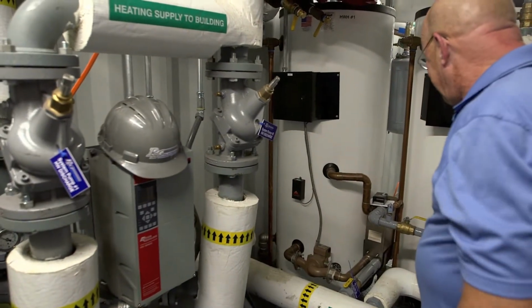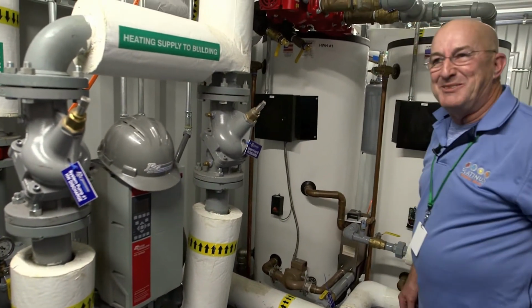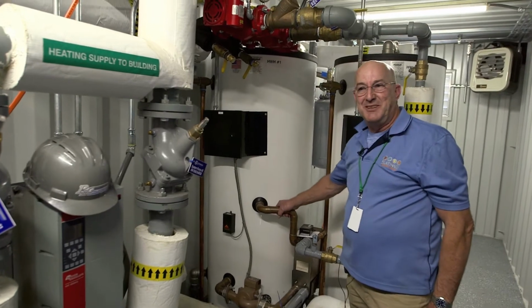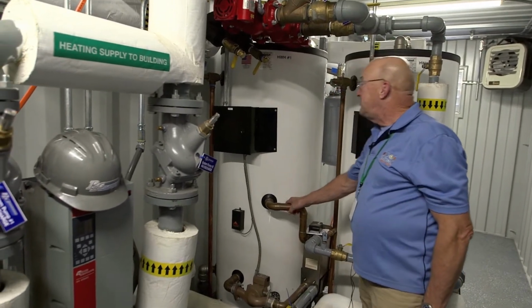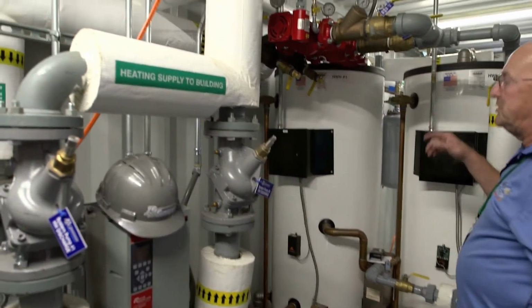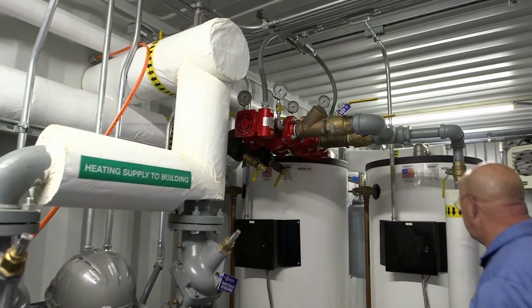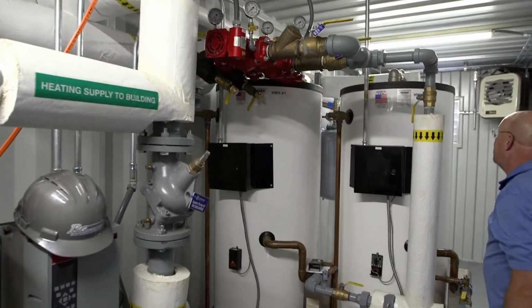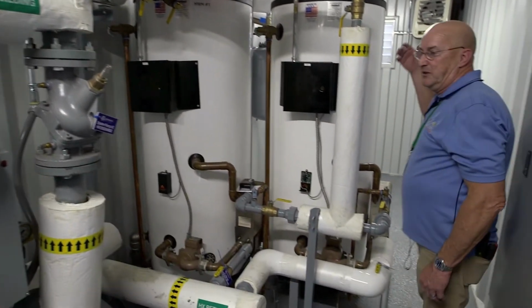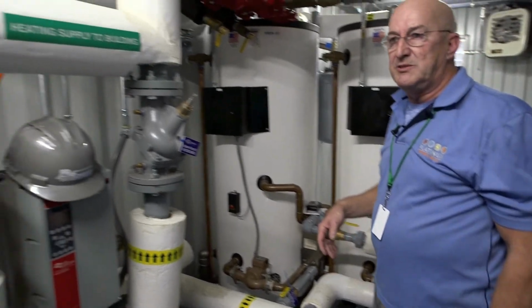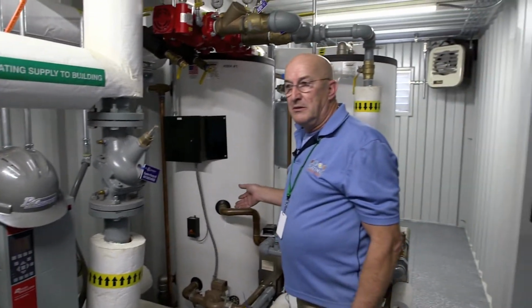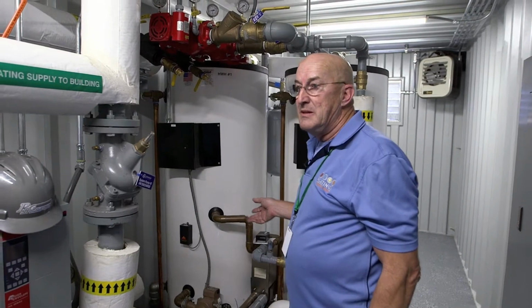I'm a little flabbergasted at that, but there's no shut-off valve on the domestic side of it. So if the pump had to be changed, the only way we can do it, and it's not a big deal, probably because of space constraints, is we'd have to shut the hot and cold water feeding the tanks. Why would you just switch tanks? Huh? Turn one tank off?